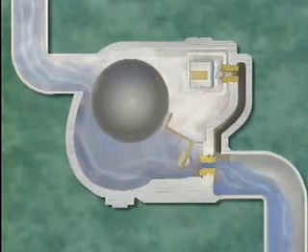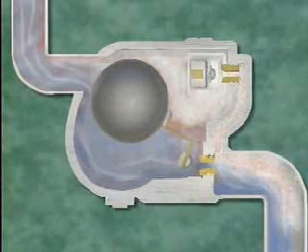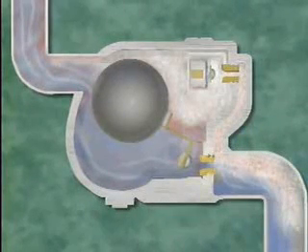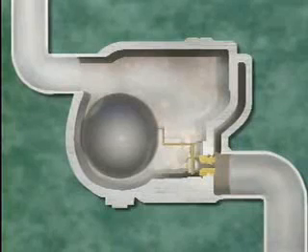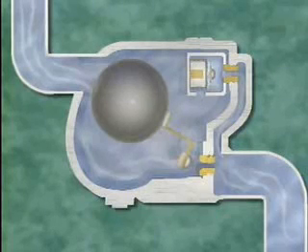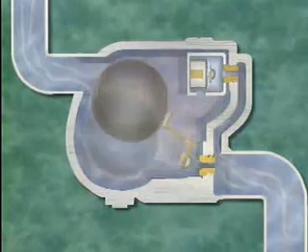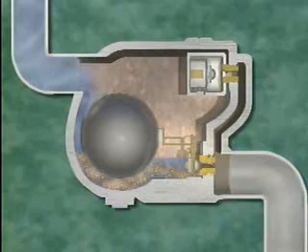The buildup of air and gases in the trap lowers the temperature and eventually causes the bellows to contract, which opens the vent valve. Then the air and gases are discharged through the trap outlet. The reaction of the bellows to temperature changes enables air and non-condensable gases to leave the trap and keeps the trap from becoming air bound—the condition that results when air fills a trap, closing the trap valve and keeping the trap from operating. If operating conditions cause condensate to build up to the point that the trap becomes waterlogged, the relatively cool condensate causes the bellows to contract, which opens the vent valve, and the condensate drains through the open vent to the trap's discharge line.